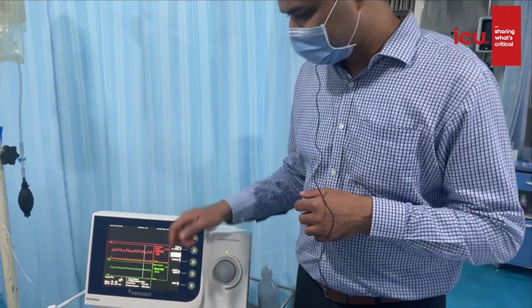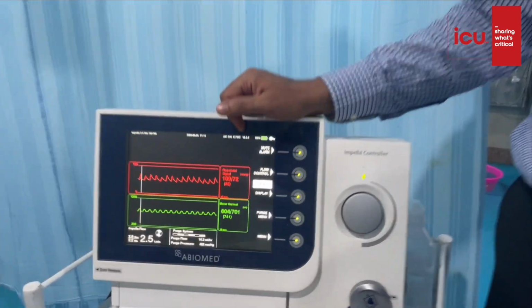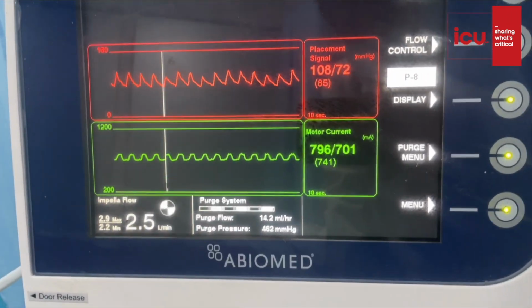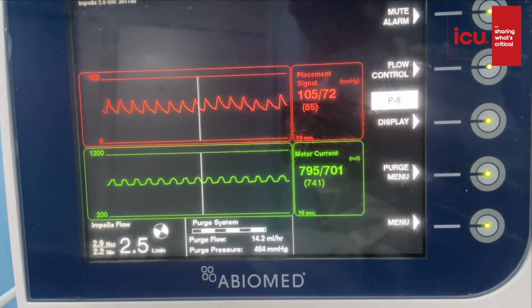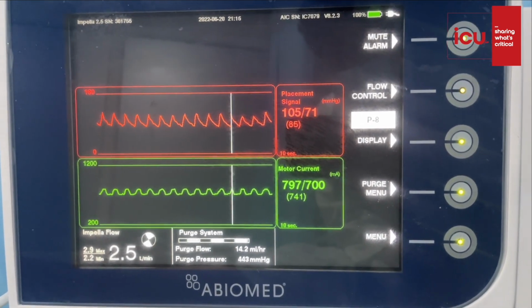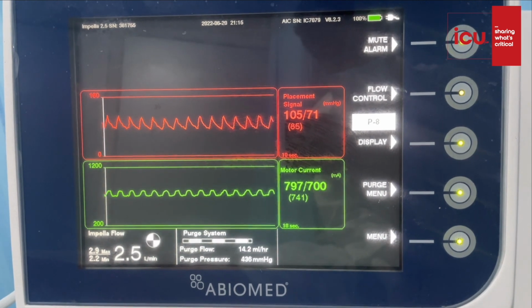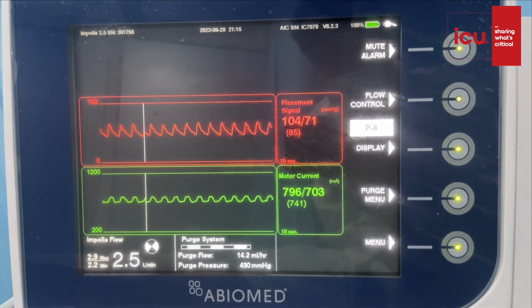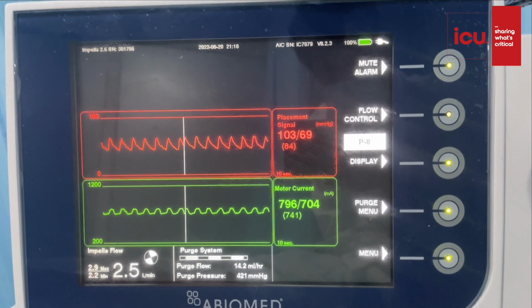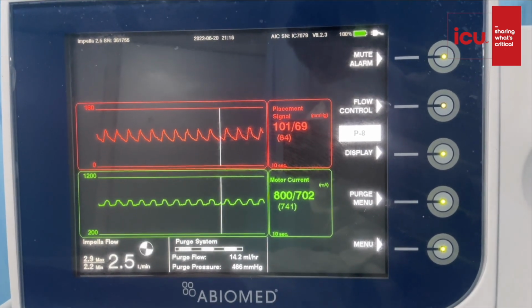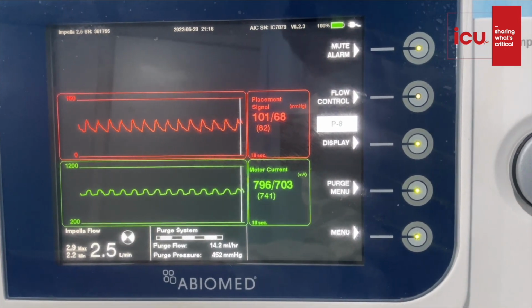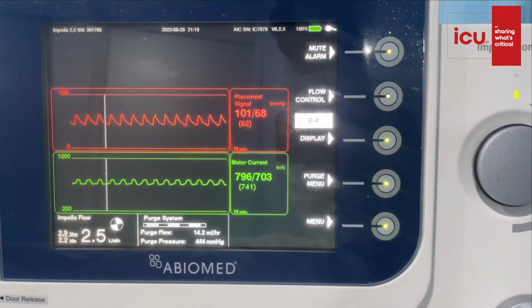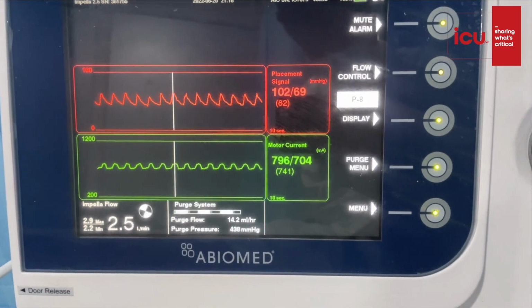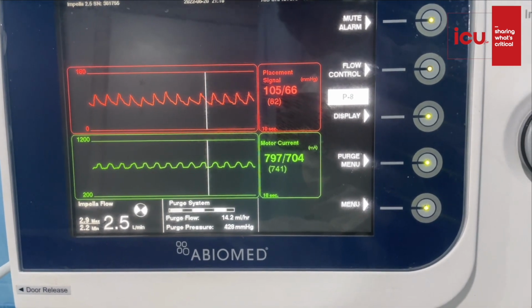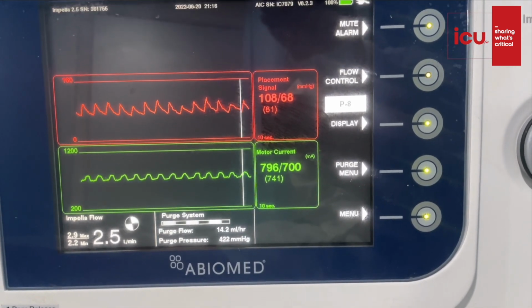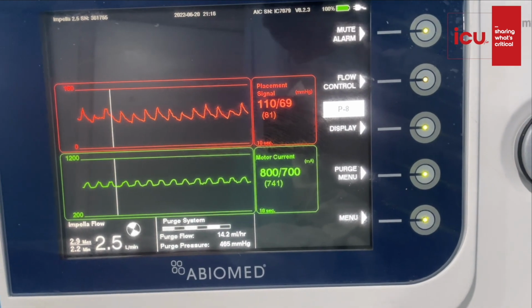Now coming to another waveform you can see in green, which we call the motor current. So Impella has a motor and that rotates at a certain RPM, creating suction. For this motor to displace the blood from one chamber of the heart to another chamber of the heart, the motor has to create a certain amount of electricity, which is measured in milliamperes, and this electricity varies with every beat of the heart. So the motor current in short is nothing but the amount of electricity generated by the motor.